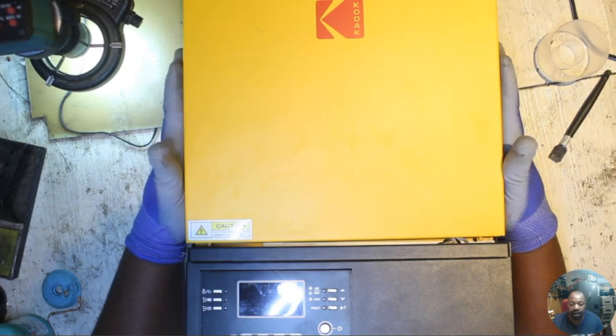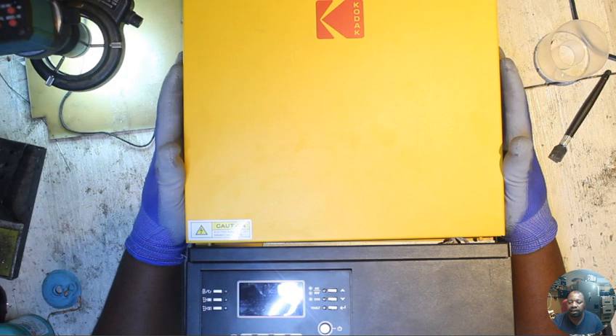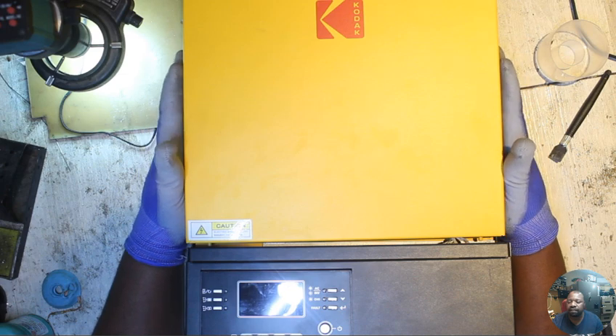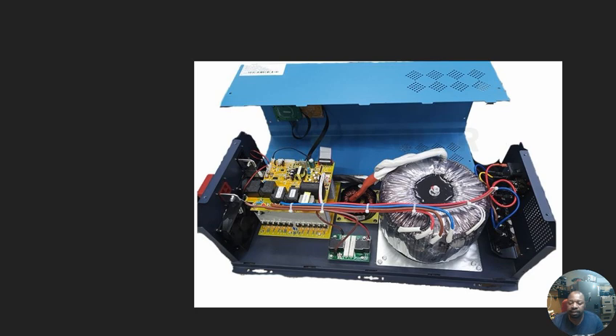This one is a high frequency inverter - they both give 230 volts out but the technology the manufacturer used is different. The low frequency inverter is more robust. Let me show you an example - this one here is a low frequency inverter. It's actually called a transformer-based inverter because the components are not as many as the high frequency inverter. On the low frequency you only have this board and the transformer, then your output. There are your DC input and the mosfets underneath, then it goes to the transformer and out.